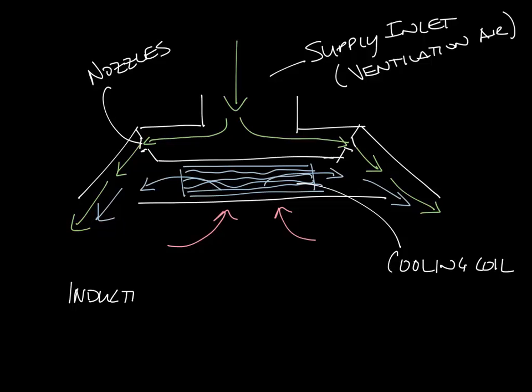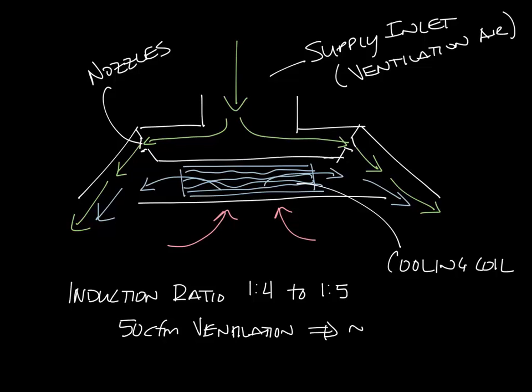A typical induction ratio for a chill beam is about 1 to 4 or 1 to 5. What that means is if you have 50 CFM ventilation air that's inducted to the unit, you'll get somewhere between 200 and 250 CFM of air in your space to handle your cooling load.